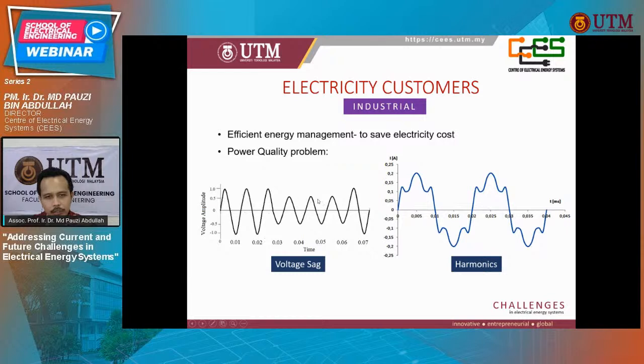But if you look here, this is a drop in amplitude - this is a voltage sag problem. It's not long, just a few milliseconds. And if you look at the next graph, this is harmonics. It's supposed to be a sinusoidal shape, but you have a strange shape, like a ghost or whatever - this is harmonics.